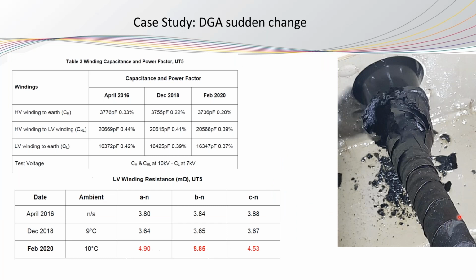In the offline testing, the power factor and capacitance didn't show anything abnormal when compared to the measurements taken before in 2018 and 2016. But when they did the DC winding resistance test at the low voltage side, there was a significant difference in the measurement of phase B compared to phases A and C, and this difference didn't exist in the previous test sessions. So the decision in the end was to go further, open the transformer, and do a visual inspection.